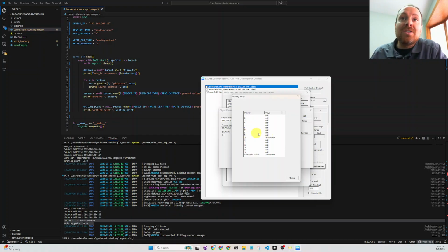So in the building automation system under the hood, the building operator can override points, HVAC set points, commands, and their writes will come up on priority 8. And then typically 9 through 16 is left for supervisory level control of the building automation system. So the building operator can still override values if they need to override the flow set points or whatever command.